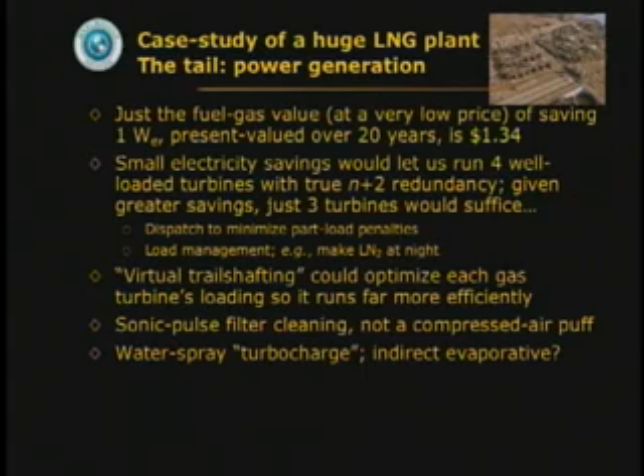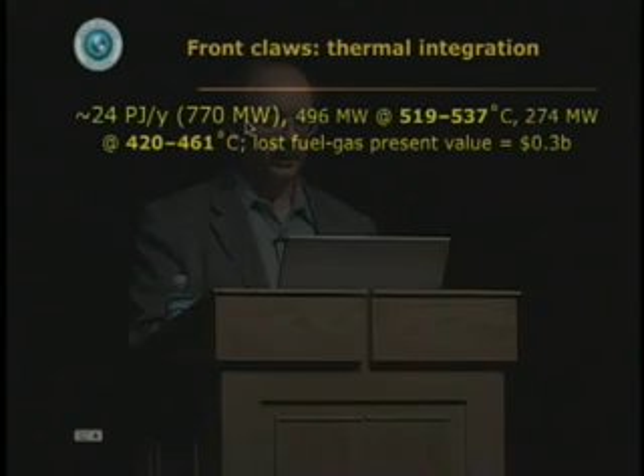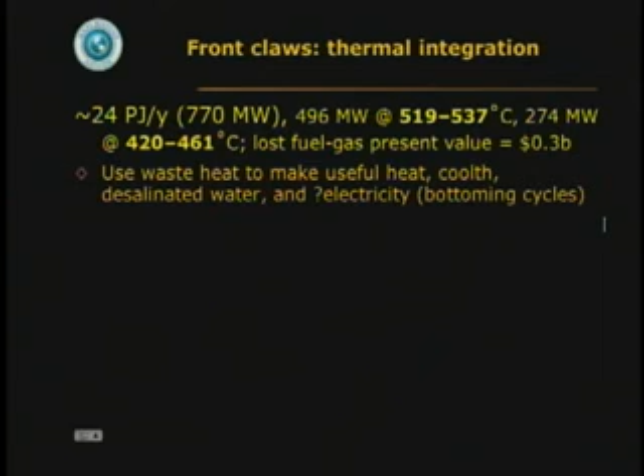Okay, the front claws of the lobster are thermal integration. This plant is throwing away 3/4 of a gigawatt of heat, mainly at very high temperatures. That's about 0.3 billion present value dollars worth of fuel at a very low cost. But that heat is so valuable. You can use it, of course, not just for useful process steps, but for making cooling, for desalinating water, and to make electricity, to eliminate furnaces and electric process heat that the plant now has. Then you cascade the heat to successively lower temperatures and milk out all the rich, meaty goodness until there's nothing left but the squeal.